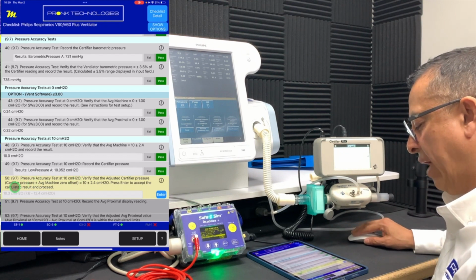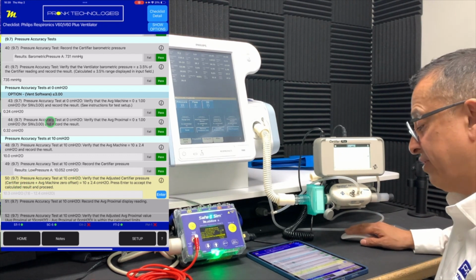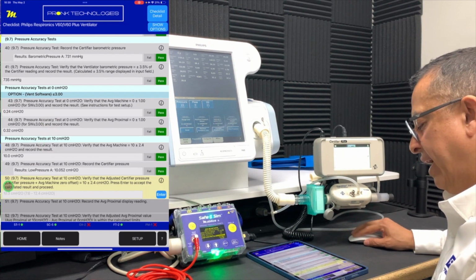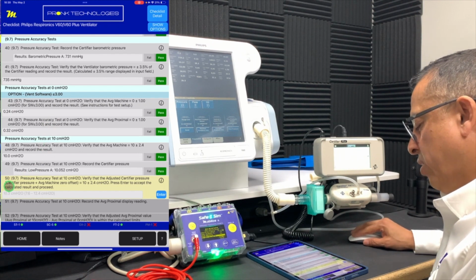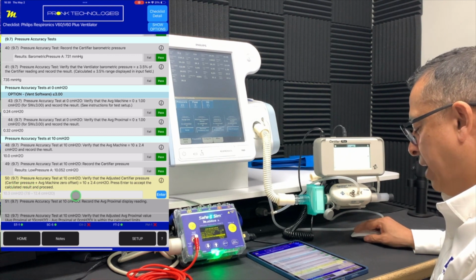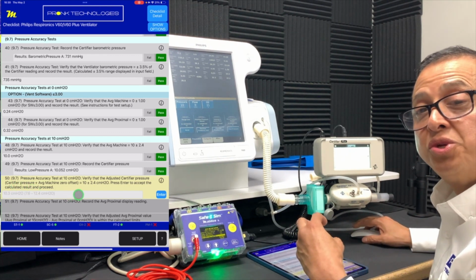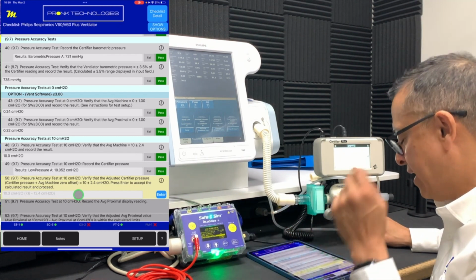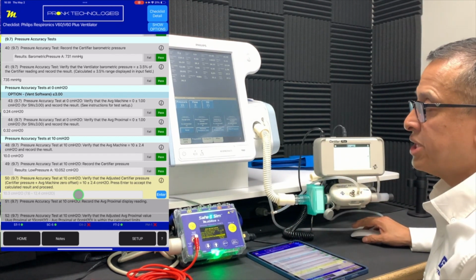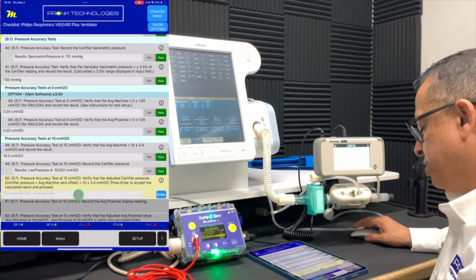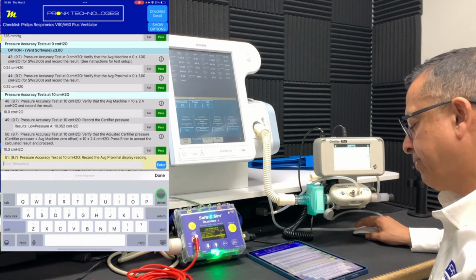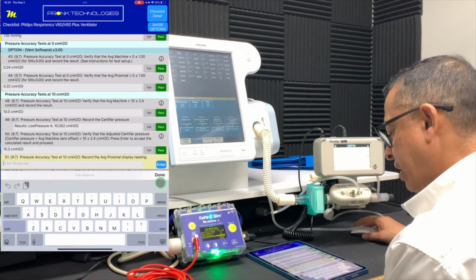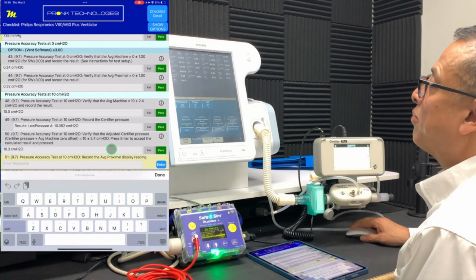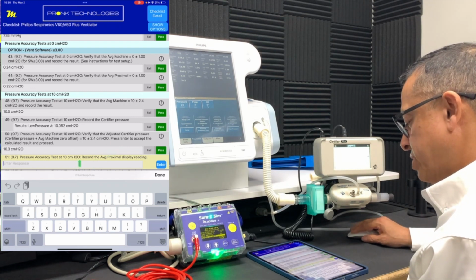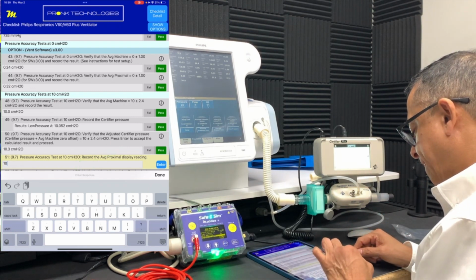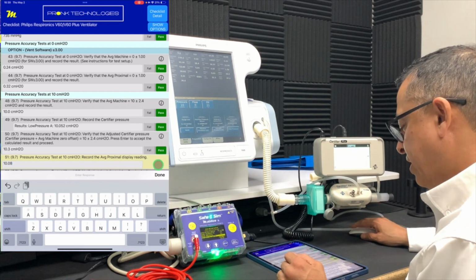And down below, that calculation's already been made based on the results we previously entered. So you can see here we have a calculated measurement of 10.3 centimeters of water, which is within range. Having these calculations built into the procedure just eliminates the manual calculations you have to do. The V60 has various calculations that have to be done, as well as some other ventilators. So the procedure really helps streamline that process and minimize any errors. Now we need to record that average proximal display pressure, and we're at 10.08. And we've done that test.